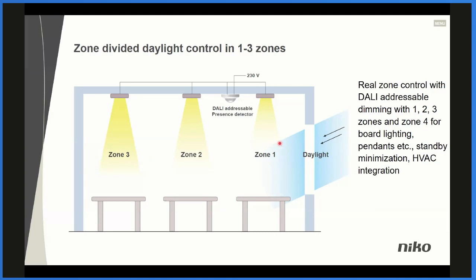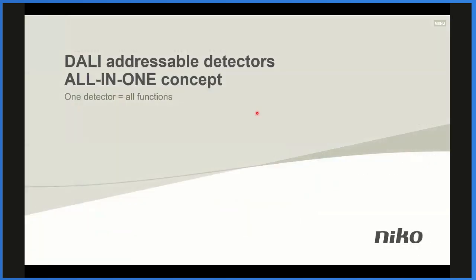The idea of daylight control is that we can dim the luminaires according to the incoming daylight. That means the light zones nearest to the incoming daylight have to be dimmed more than the other two zones. The detector is mounted on the ceiling and measures both artificial light and incoming daylight. According to how much incoming daylight we have, the detector will automatically dim the luminaires. To do that, we have different kinds of solutions.